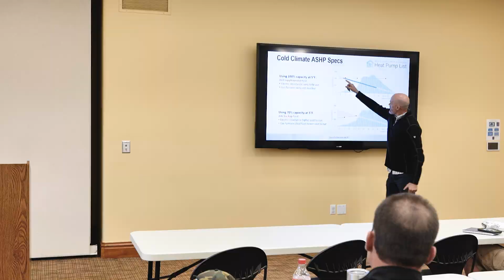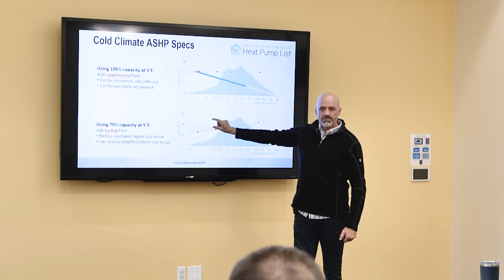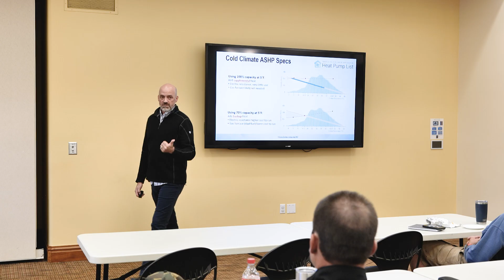On the bottom half here, this is at 70% capable, and you can see these gray areas—that's the supplemental or potentially backup heat if the system stops. This is a much larger supplemental heating system you have to pay to install and to run. So I'd say focus on the 100% capable system, not the 70% capable one.